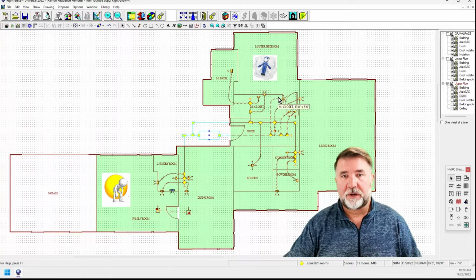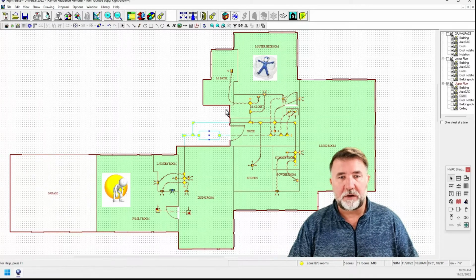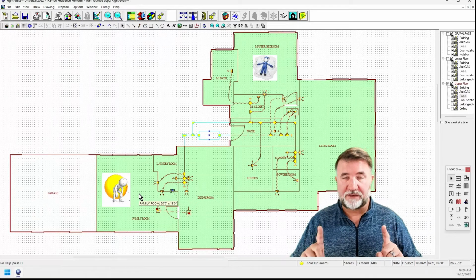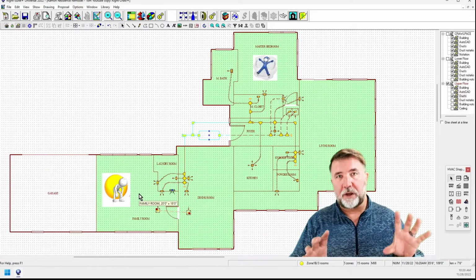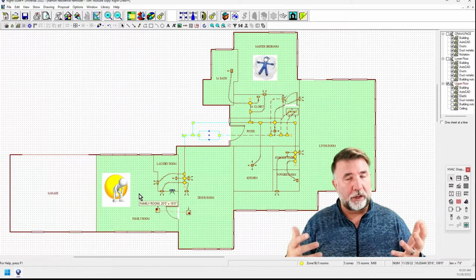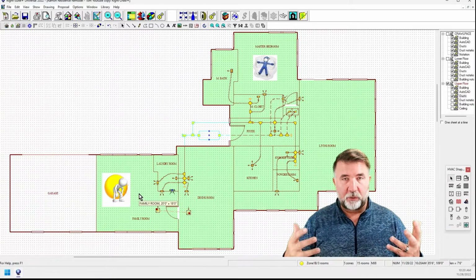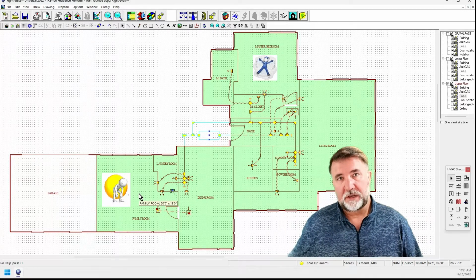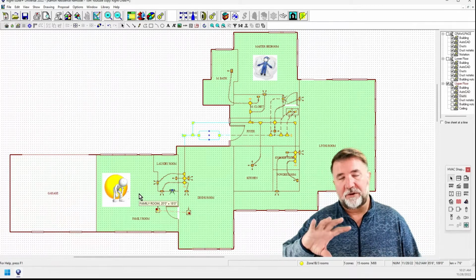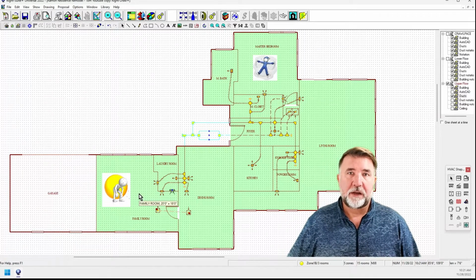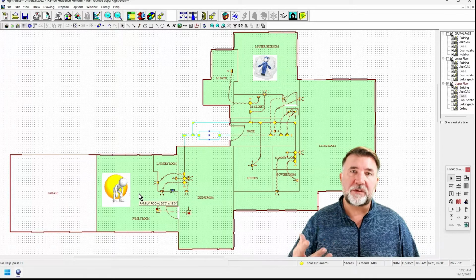of each other. So whether I'm in this room up here or in this room down here, if I properly design the system, size it, put the right amount of CFMs into the room, the right returns, and install it properly, and it's running the way it should, you should have rooms within 2 to 3 degrees of each other easily. We're going to do a whole other video on installation. But these are the two biggest reasons.